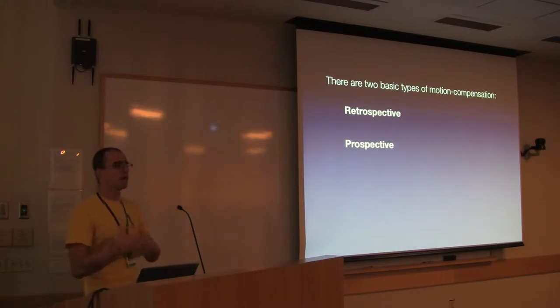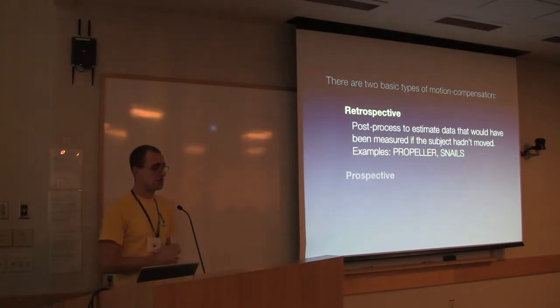I'm going to break these down into two very broad categories. One is retrospective motion compensation and the other is prospective motion compensation. In retrospective techniques, we post-process the motion damaged data. I do my six-minute scan, some of it's motion damaged, and I'm going to do post-processing to try and estimate what I would have measured if the subject hadn't moved. There's lots of methods for this with names like propeller, blades, snails. Basically what these techniques are doing is attempting a synthesis of the image you would have gotten. Invariably there's some tradeoff because you didn't actually acquire the right data.